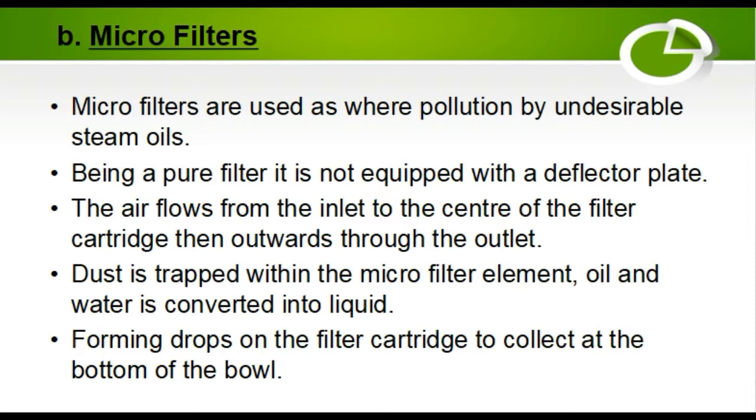Microfilters are used to remove pollution by undesirable steam and oils. Being a pure filter, it is not equipped with a deflector plate. The air flows from the inlet to the center of the filter cartridge, then outward through the outlet. Dust is trapped within the microfilter element, and oil and water are converted into liquid, forming drops on the filter cartridge that collect at the bottom of the bowl.